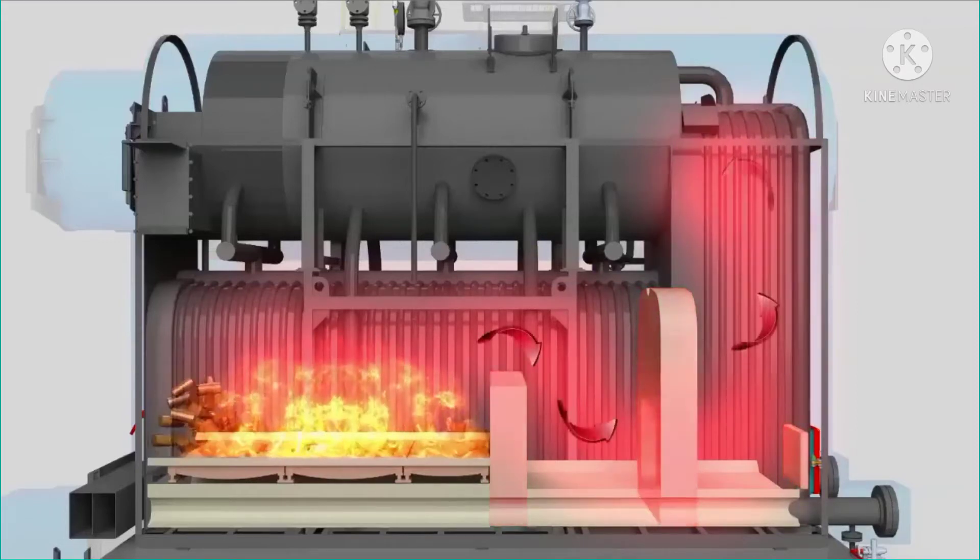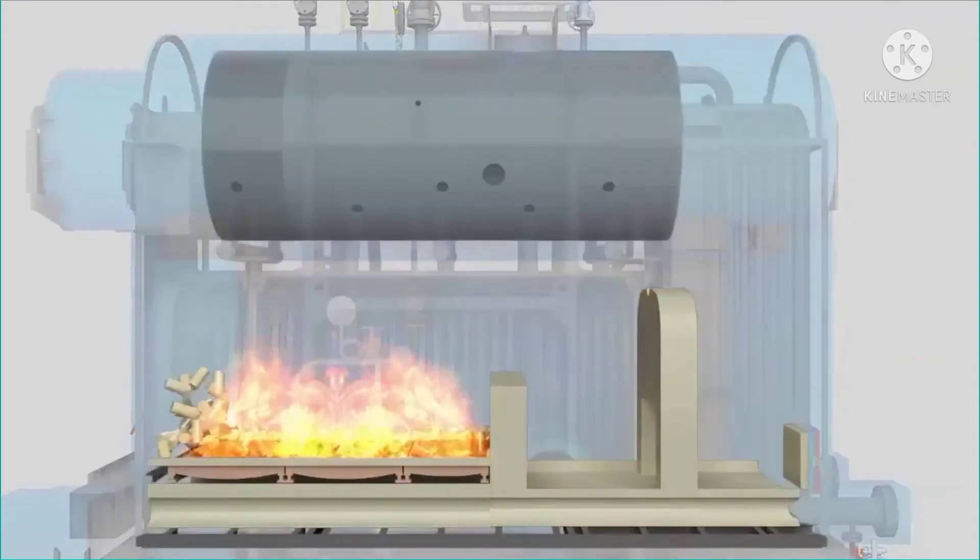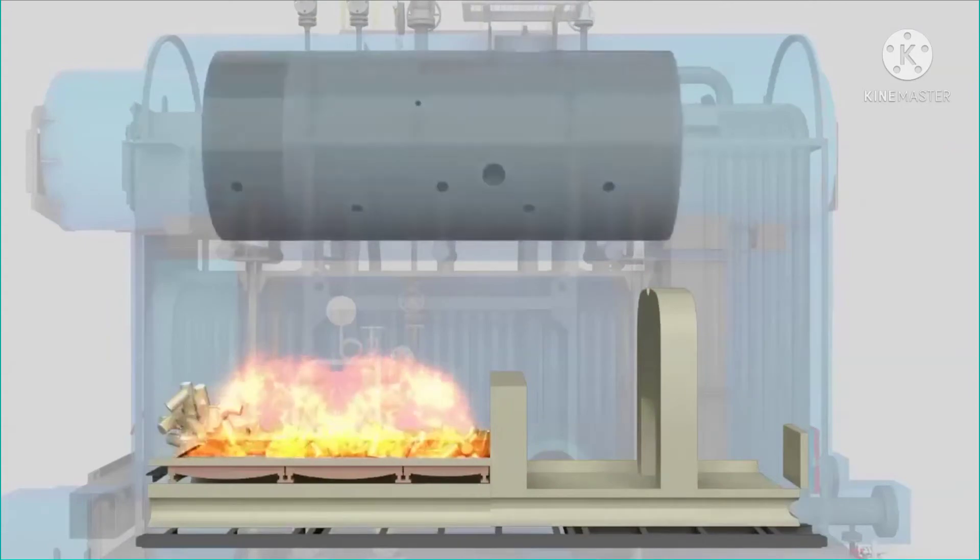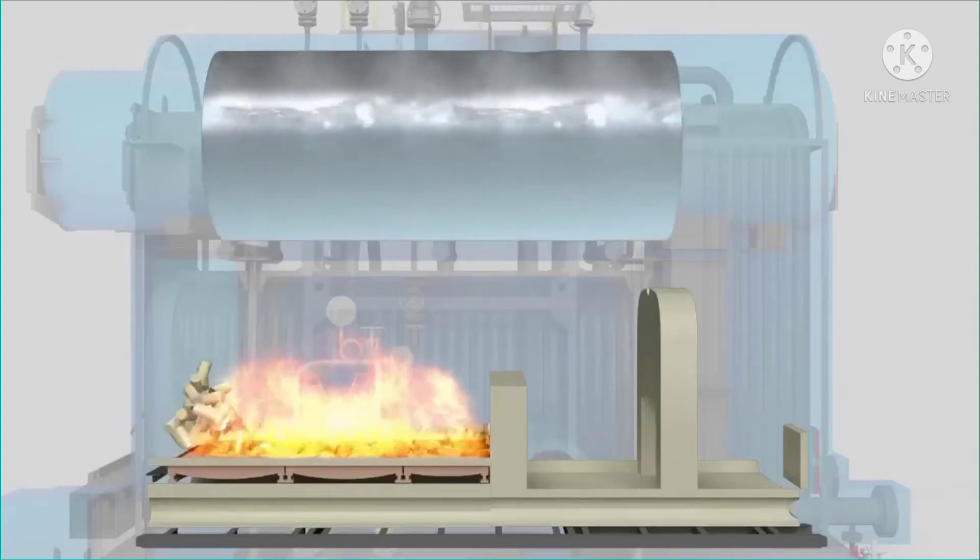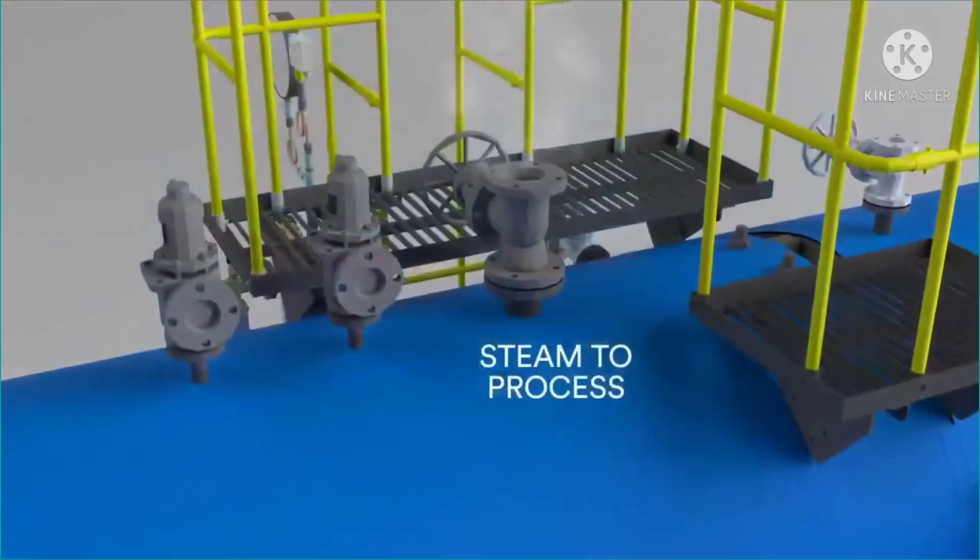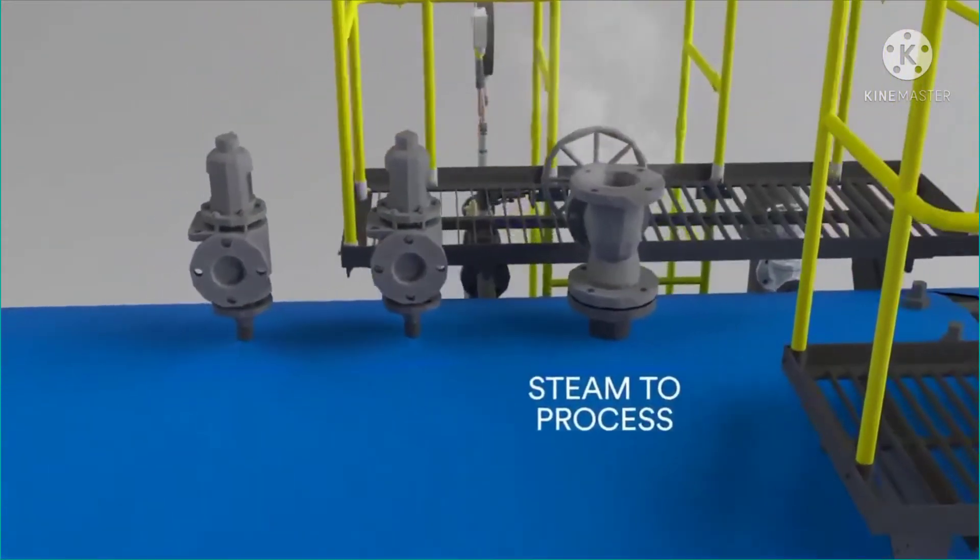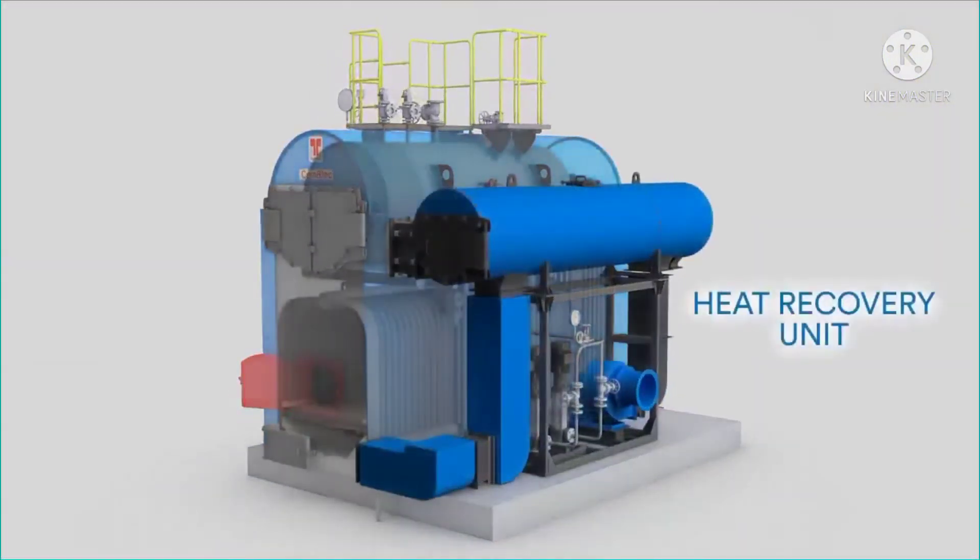The steam drum is a vessel of water with tubes placed inside it through which the flue gases flow. In this drum, the water is again heated and the steam rises up in the top portion of the drum. The steam is then taken away from the main steam stop valve and the flue gases are exhausted through a smoke chamber to the heat recovery unit.